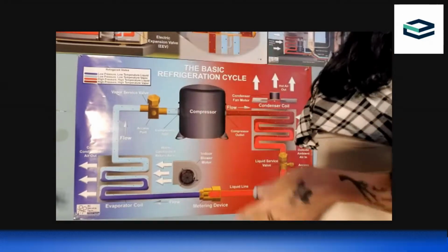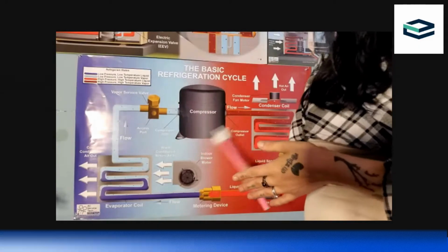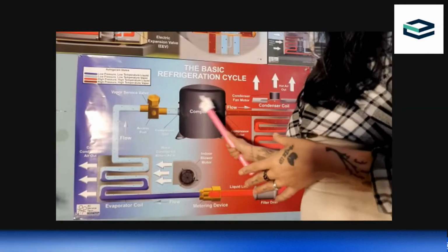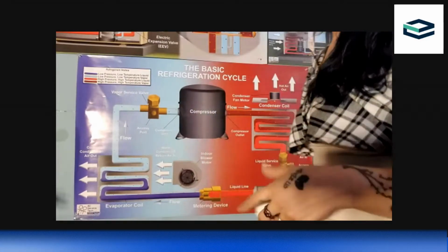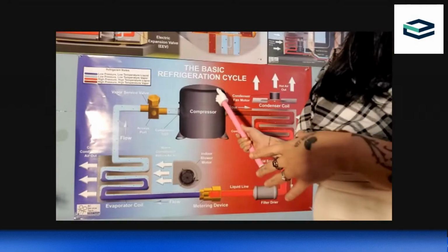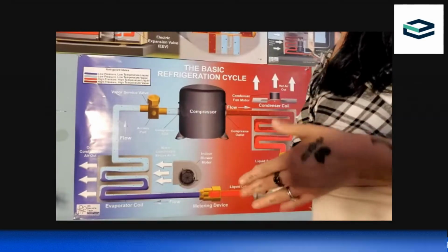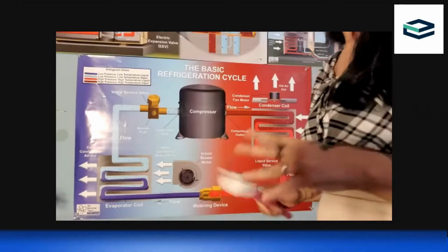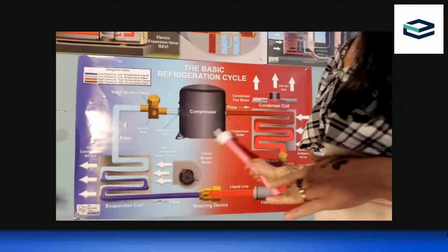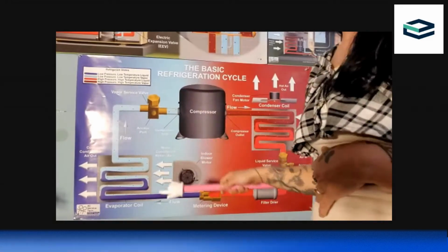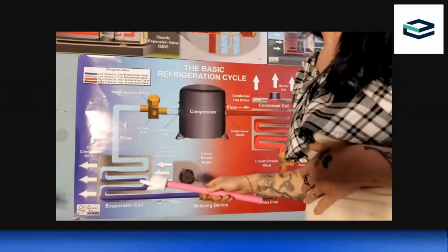So what happens is the liquid refrigerant gets into the compressor, it gets into the valves, it gets into the scrolls, depending on what kind of compressor it is, and then it causes acidity. It causes the copper plating we hear about within the compressor, and that will damage all of the mechanical moving parts of the compressor, and eventually you'll end up with compressor burnout.